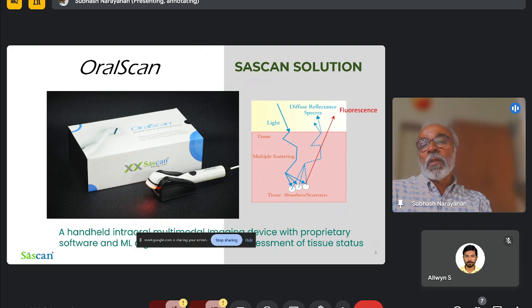The device works basically on the principle of diffuse reflectance, that is the scattering of light, and absorption and emission of light from the biochemical constituents of the tissue. So you can see that when light is falling on the tissue, or any surface for that matter, a portion of it gets reflected from the surface, and there is a specular reflection component also based on the surface irregularities. And a small portion of the light that goes inside the tissue undergoes multiple scattering, that is Rayleigh scattering and elastic scattering. All kinds of scattering happen, and the tissue absorbers that are inside the tissue, like NADH or FAD or PP9, absorb this and emit at a longer wavelength. That's the fluorescence. It's called the fluorescence.